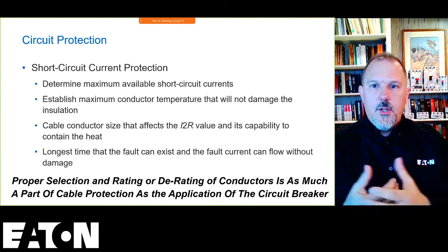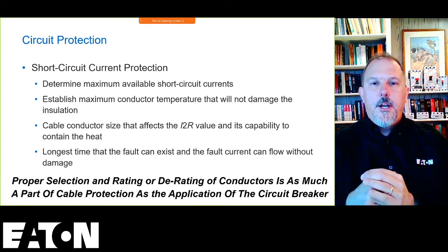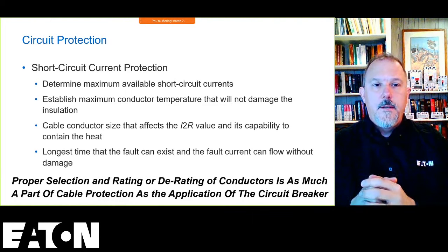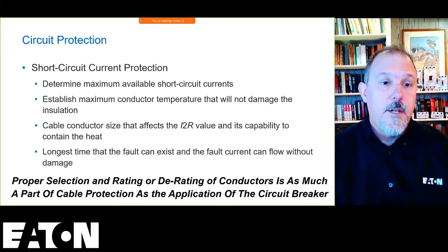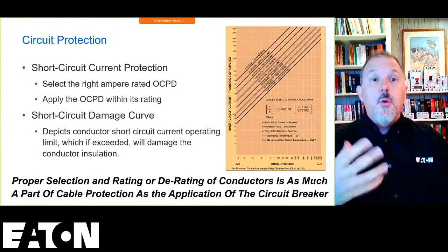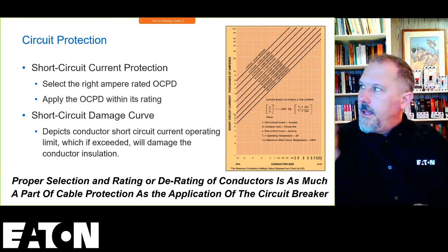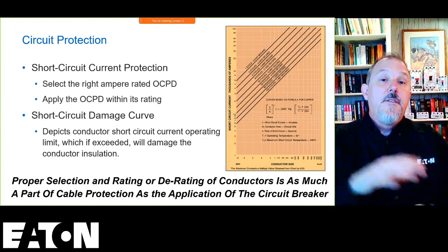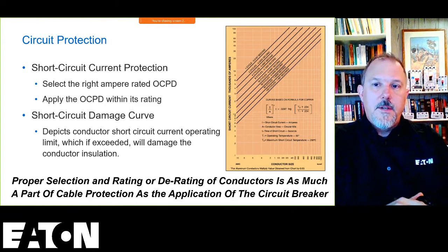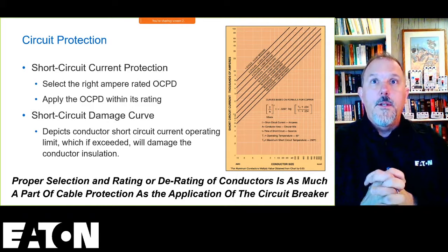So when you have a high short circuit, you're really worried about damaging that conductor to a point where you reach an annealing point, or you're going to vaporize that conductor and cause it to disintegrate, basically based upon the magnetic forces and whatnot. So we have what we call short circuit damage curves, that are basically a nice straight line. We plot those in SKM, and maybe I'll bring up my SKM. I got some plots of damage curves based on some previous plots that I've done, and diagrams that I've been able to obtain. But we can pull up some examples if we want to.